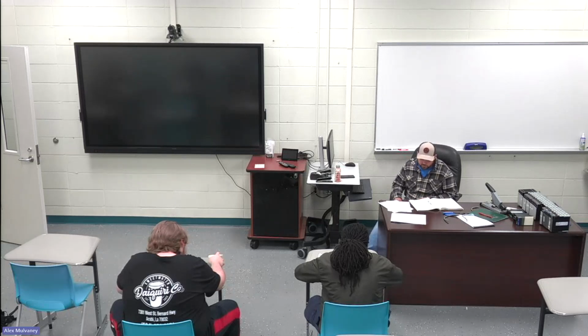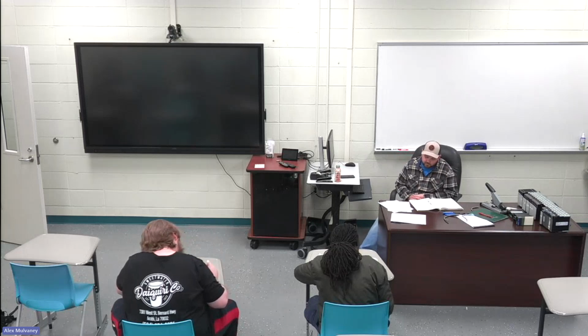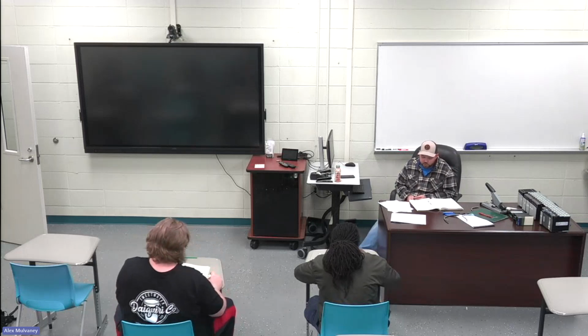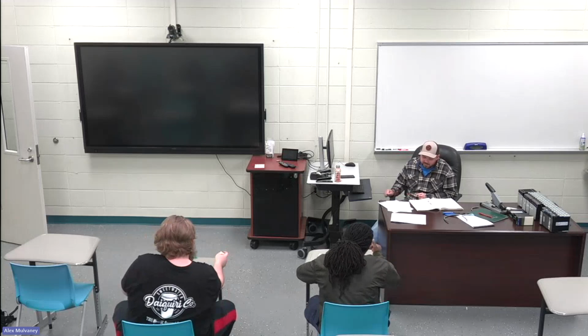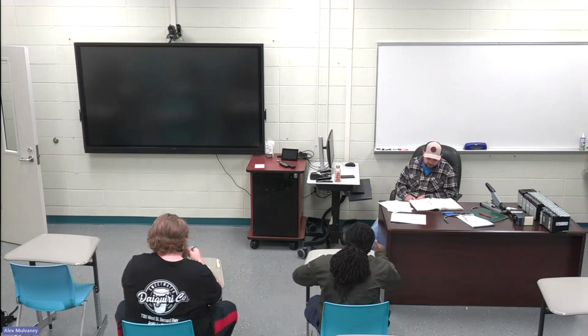The last bullet point on the page is highlighted. A ground ring encircling the building or structure in direct contact with the earth at a depth of not less than 2.5 feet. Below grade, this ring must consist of at least 20 feet of bare copper conductor that's not smaller than 2 gauge wire. Key in on a ground ring, like a ground ring has to be no smaller than 2 gauge. Key in on that 2 gauge for that highlight.